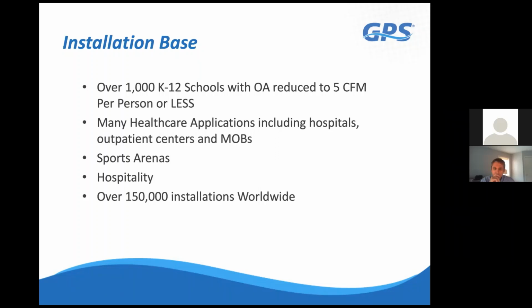So as you can imagine, if you're designing a new facility and you can reduce your outside air requirements, that will have a significant impact on first cost because you downsize the chiller, maybe the DX equipment, maybe the outside air equipment that has to treat the outside air, dehumidify it or preheat it before it's dumped into the sensible air handlers. And so there's a lot of savings involved with that.